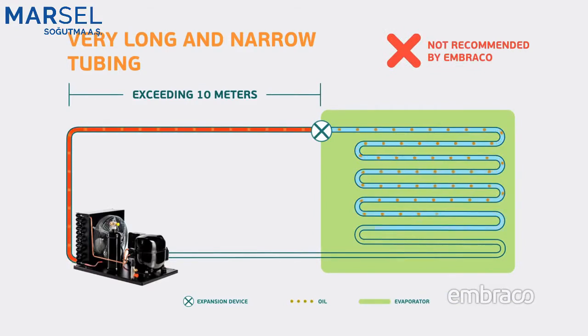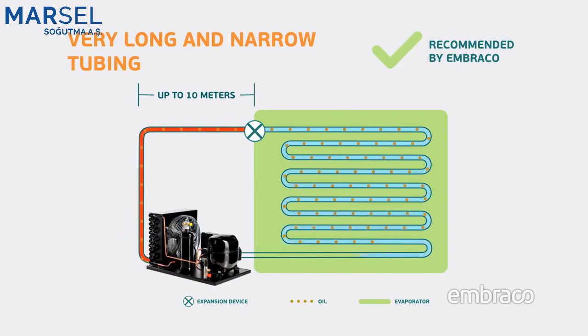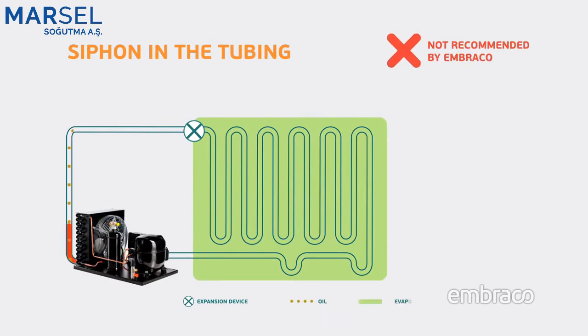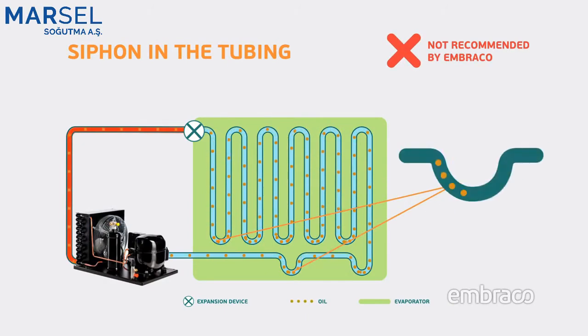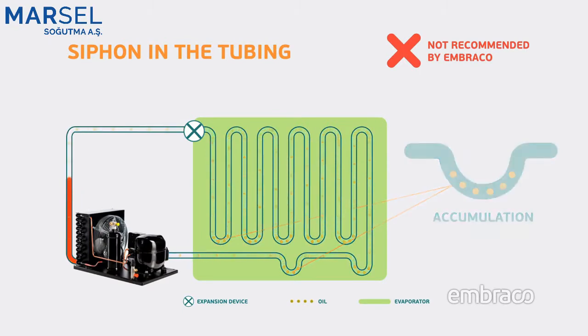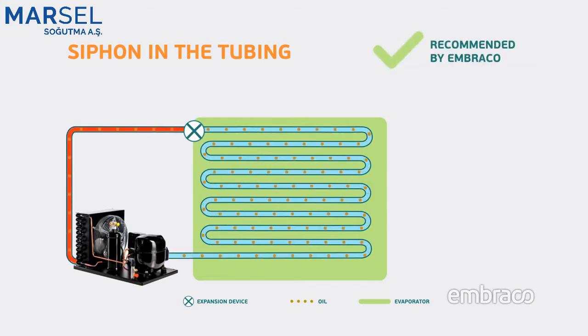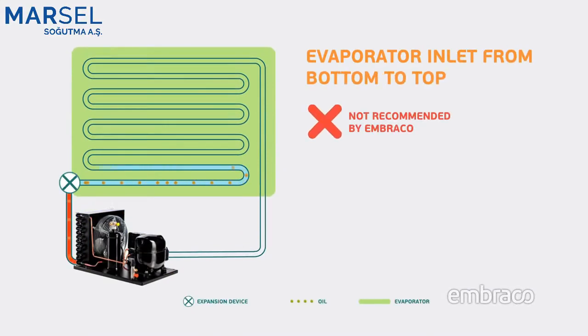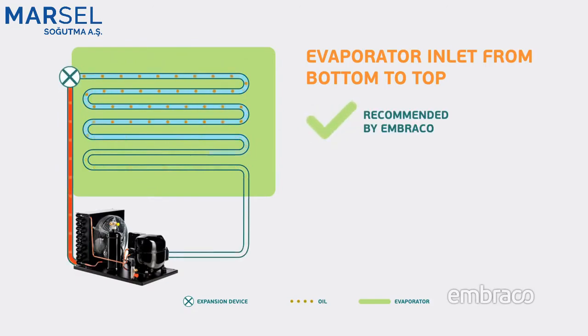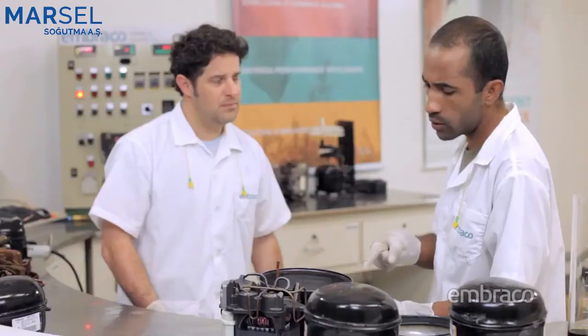When there's an obstruction in the tubing or problems in the system's sizing, the oil can't return, causing the charge to be less than ideal. Sizing problems include very long and narrow tubing, siphon in the tubing, and evaporator inlet from bottom to top. When the compressor operates with an oil charge lower than specified, there will be increased wear, which can reduce the useful life of the compressor and could create a locked rotor situation.